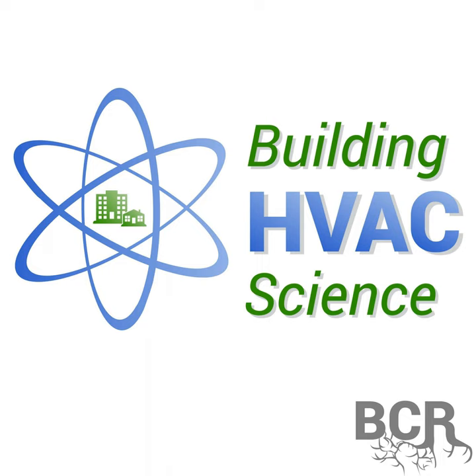So there's the cleaning. The next thing is, let's verify that airflow is within the ballpark, because a lot of airflows on these blowers, the speed setting is set at the factory and it's never changed. Or you've got a furnace or an air handler that can handle anywhere from, let's say, a 2 to a 3.5 ton. Well, chances are, if you put it on a 2 ton, it's probably got too high of an airflow. If you put it on 3.5, it might be too low, but you need to measure it, because the airflow is going to be dependent upon the coil configuration, how clean the blower and the coil are, the size of the return, the type of filter being used, and the duct system on the return and supply side. So, what are the chances it just happened to be right without you checking it?